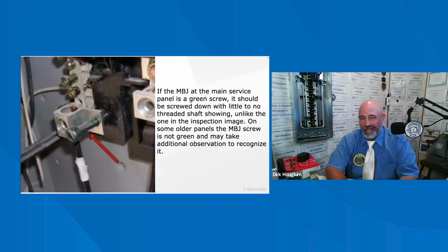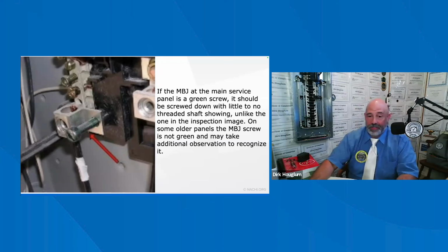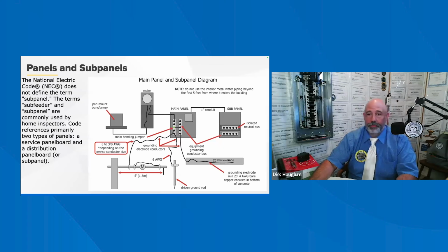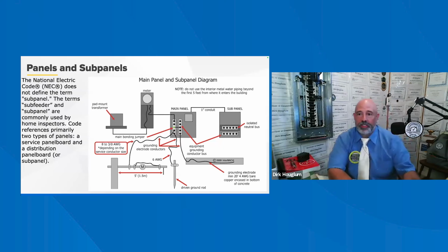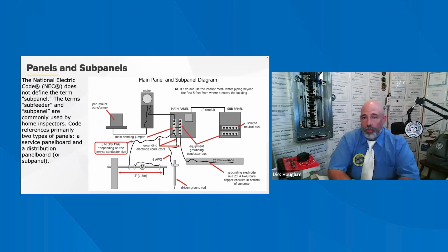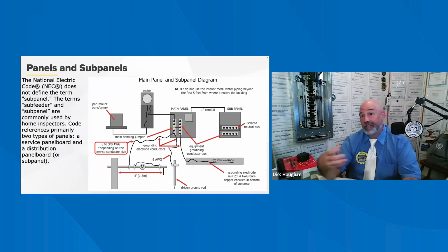But you might want to put that in as further evaluation, just in case. Just my thought. So there you go. A service panel board is a distribution or load center that contains the main disconnect, meaning the main disconnect breaker. For example, this is the only panel where the neutral and ground should be joined, bonded together.